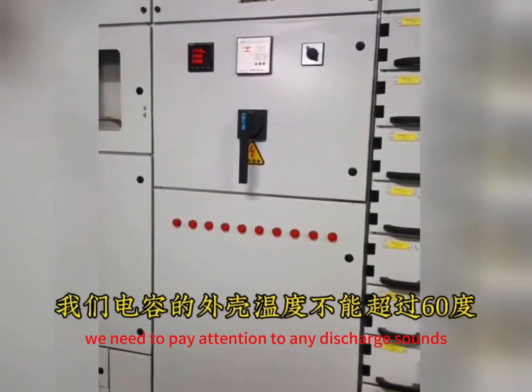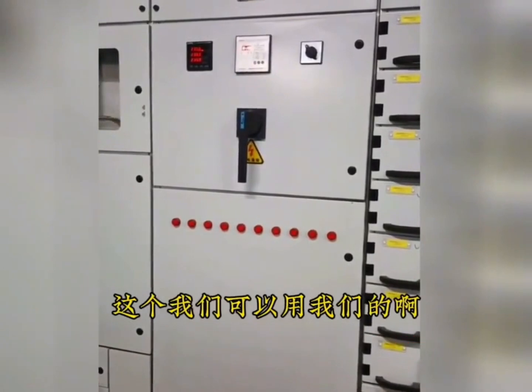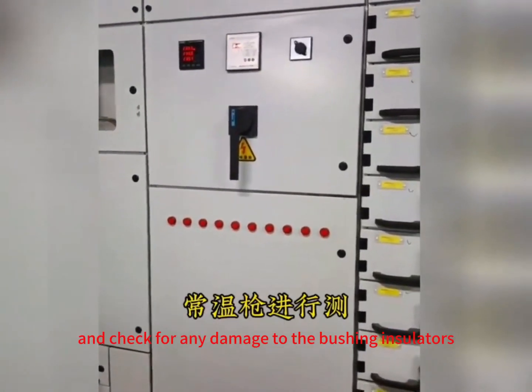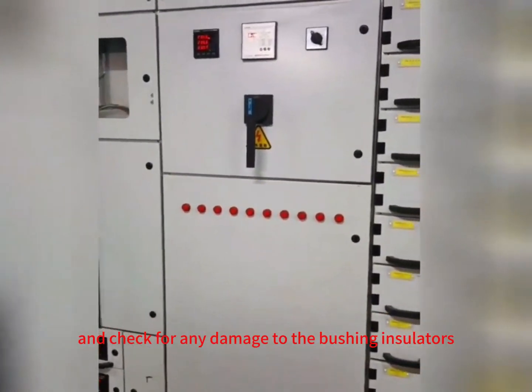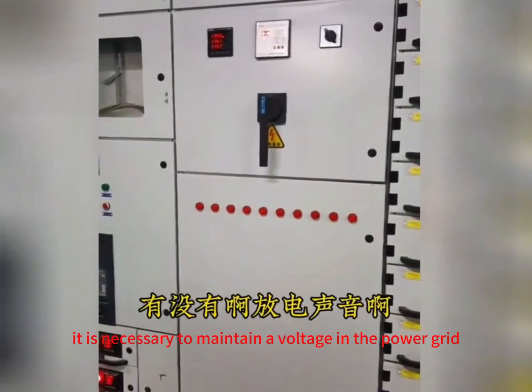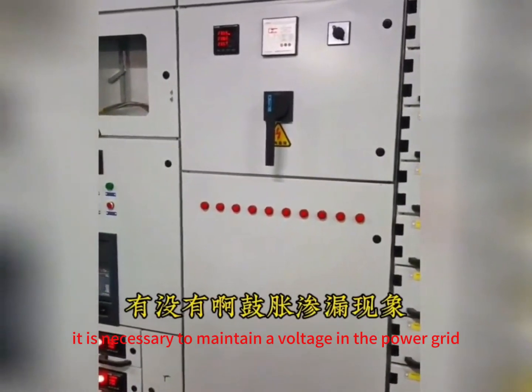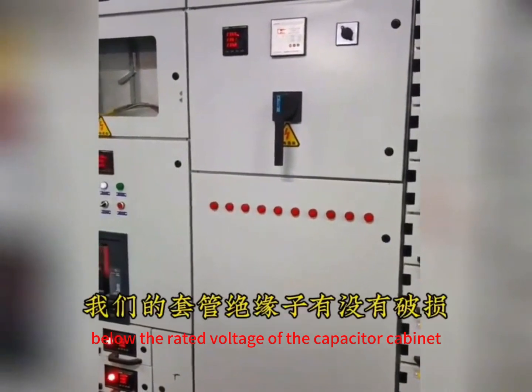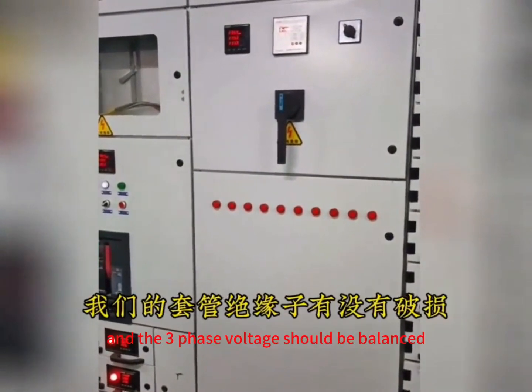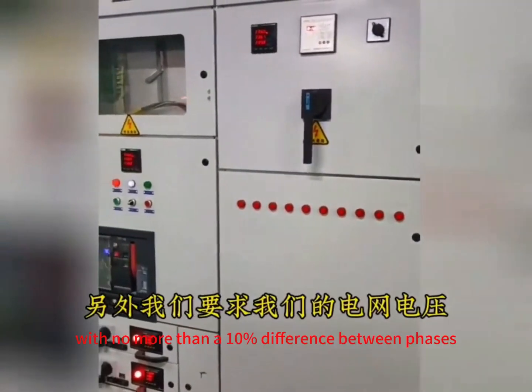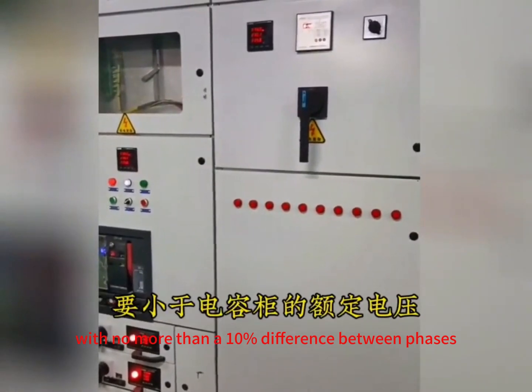Additionally, we need to pay attention to any discharge sounds, signs of faults, and check for any damage to the bushing insulators. Furthermore, it is necessary to maintain a voltage in the power grid below the rated voltage of the capacitor cabinet, and the three-phase voltage should be balanced, with no more than a 10% difference between phases.